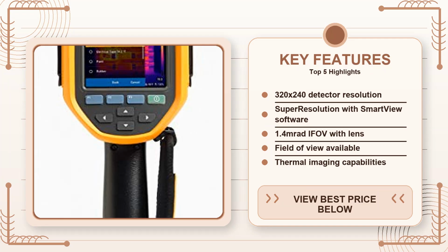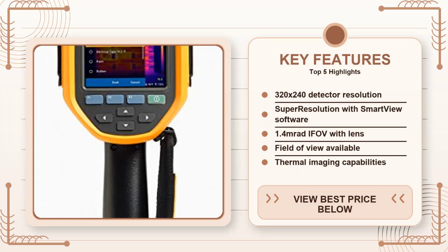Something a lower resolution unit would have smeared into the background. The other thing that matters in day-to-day use is the field of view, FOV, and the instantaneous field of view, IFOV. The Ti450 Pro's standard lens gives you a decent balance, a wide enough view to capture an entire equipment bay, but still tight enough that you can isolate a specific component without the image becoming a blurry mess.